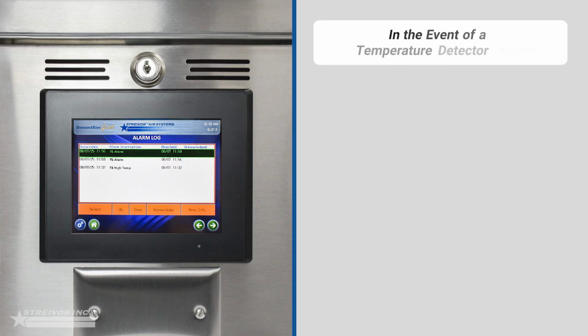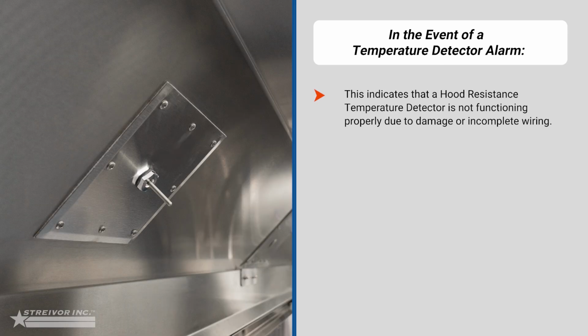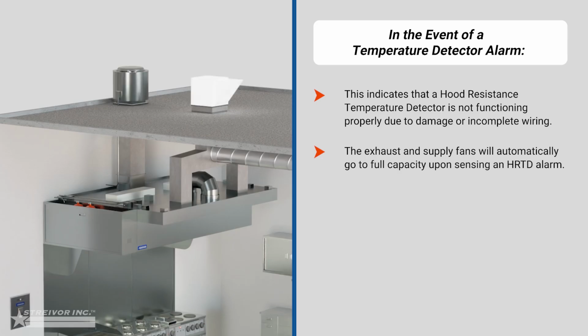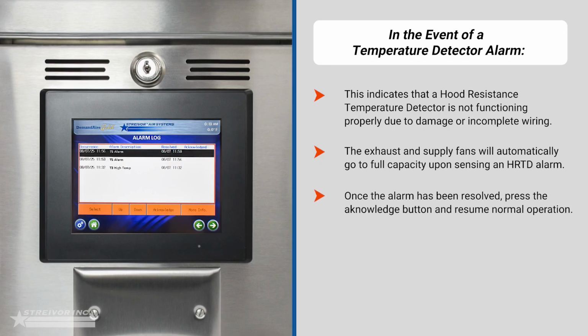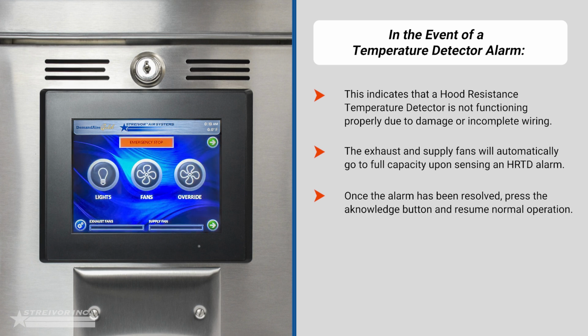In the event of a temperature detector alarm, this indicates that a hood resistance temperature detector is not functioning properly due to damage or incomplete wiring. The exhaust and supply fans will automatically go to full capacity upon sensing an HRTD alarm. Once the alarm has been resolved, select the TS alarm using the up and down buttons. Press the Acknowledge button and resume normal operation.